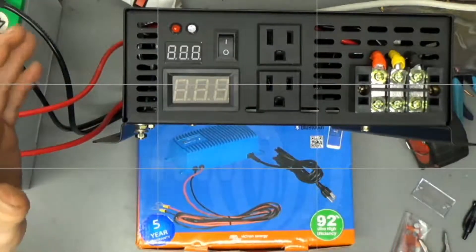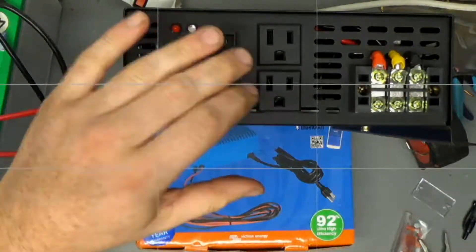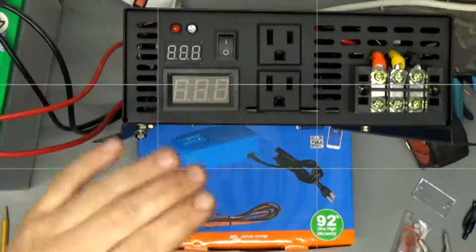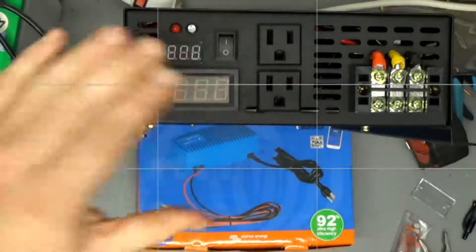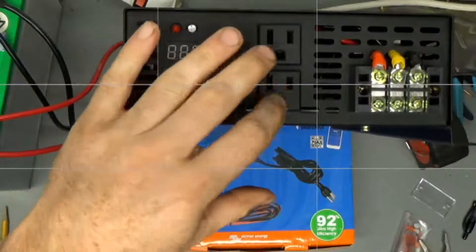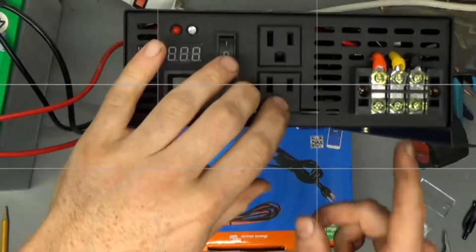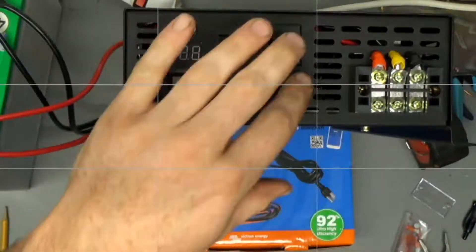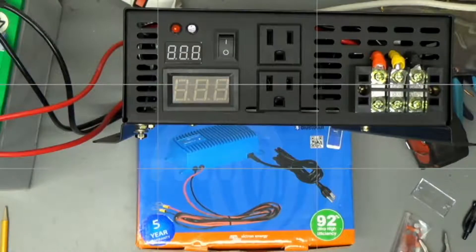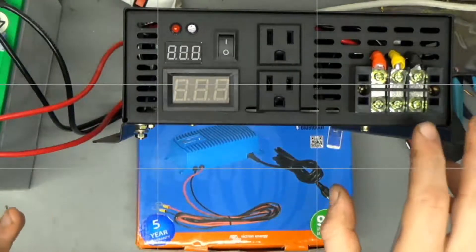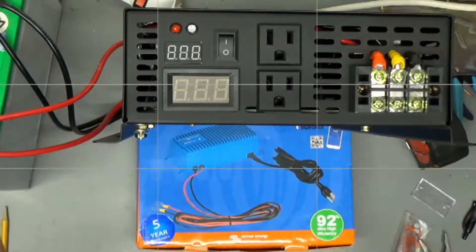But in any case, this works okay. I mean, it's not ideal, but this works okay when you're just plugging shit into these receptacles. You plug your power drill into this thing and maybe the metal enclosure is attached to the ground. But that's fine because the neutral isn't bonded to the ground inside of your power tools and it just magically works. Now if you did touch the neutral while you were holding, you could still shock yourself. It's not ideal, like I said.